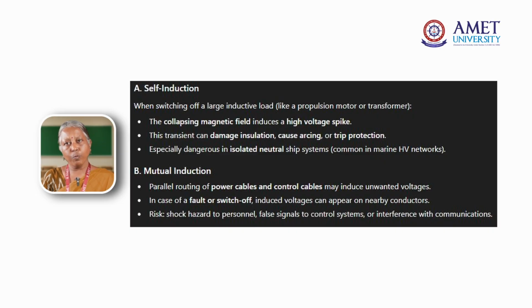Then if you are not following the safety rules, a fault may occur and that will affect the person who is working with it. Due to self-inductance and mutual inductance, there is also a possibility of energy storage inside the motors even though the motor is switched off. The energy stored in the inductance has to be earthed. Suppose a person is going to rectify a problem in a motor, then these charges have to be discharged, and only then should a person be allowed to rectify the problem. Even though the motor is switched off, you should be aware that the charges inside the motor are discharged through earth. Then only you will be safe when you operate or rectify the motor problem. So these are the hazards which will occur onboard due to high voltage.